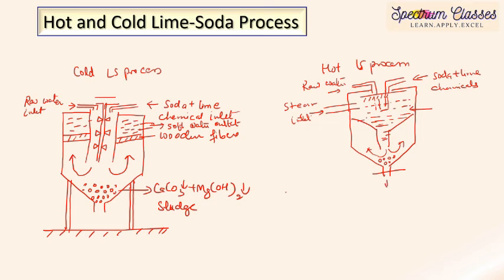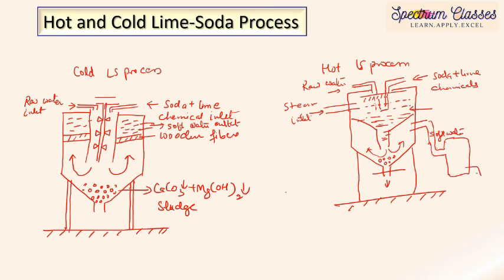In the hot process, soft water is collected from the soft water outlet, while sludge particles exit through a sludge outlet. Since fine suspended particles remain, coagulants are added, causing them to agglomerate. The water then passes through an external filter containing three layers: fine sand, coarse sand, and gravels, to produce the final soft water.